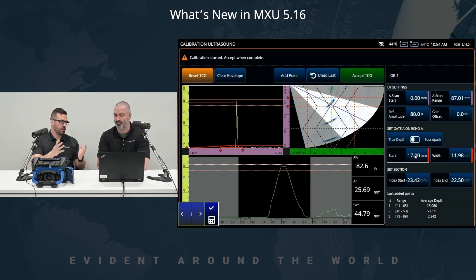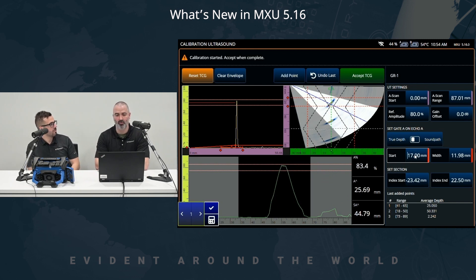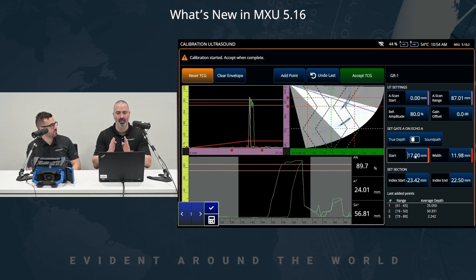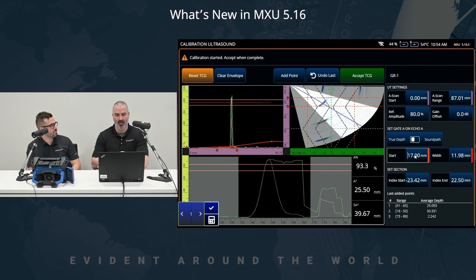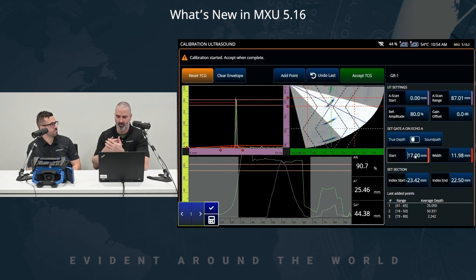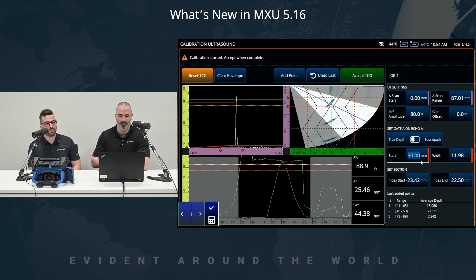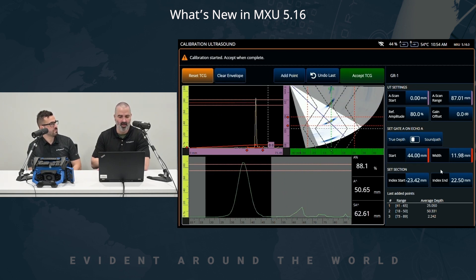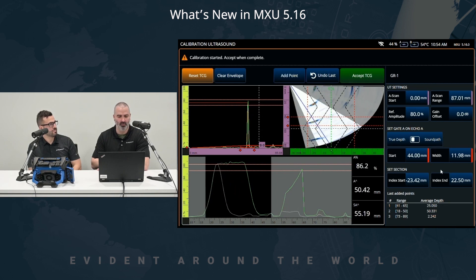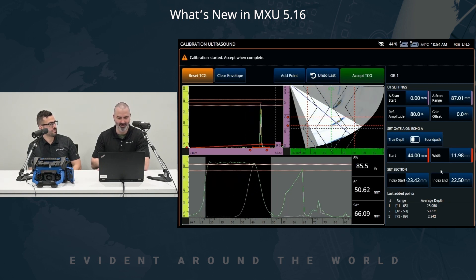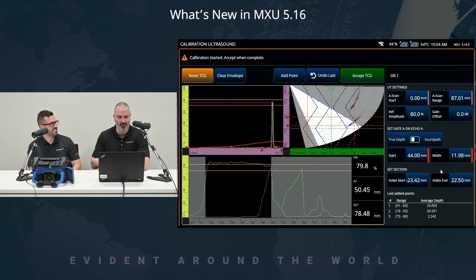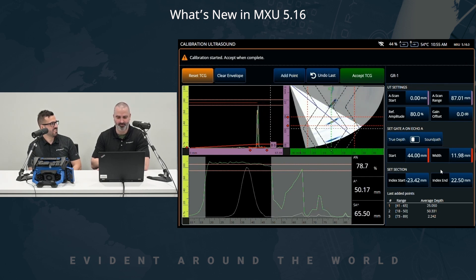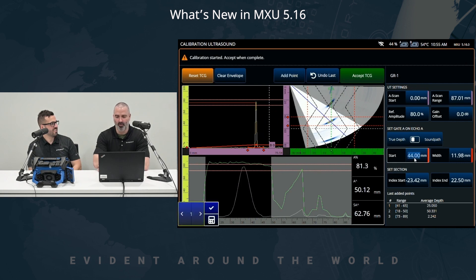Going back and reviewing, we are at the reference level again — so any notch, any crack, anything before the weld is now also calibrated for the inspection. The weld overlay is now accessible directly from the TCG calibration, meaning you only aim at that section. That's a very good point — the index limiters and the weld overlay really had to come hand in hand. Going back to our calibrated reflectors and side drill holes, we can validate that we are still within or close to the tolerance lines.